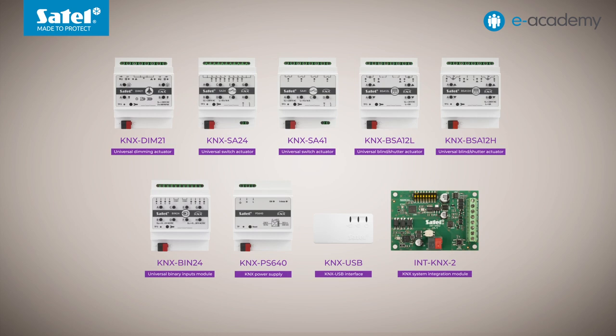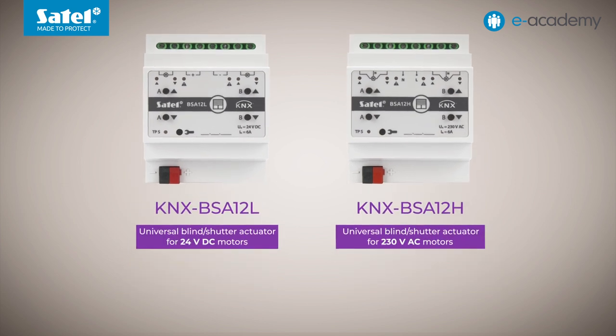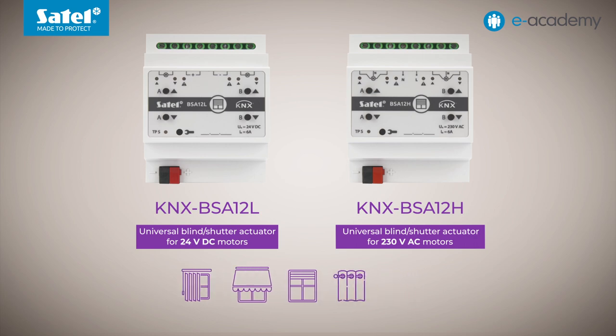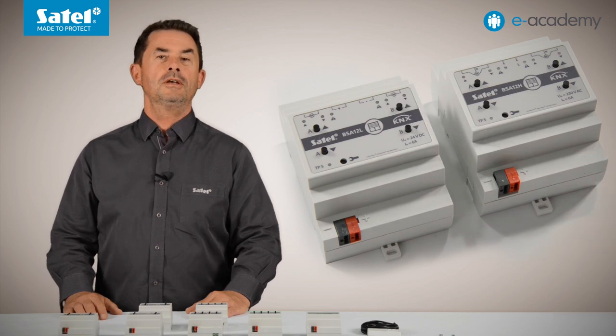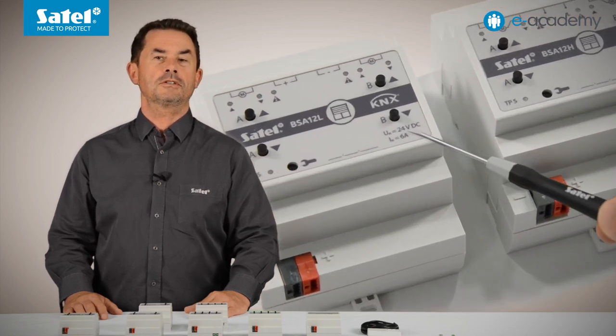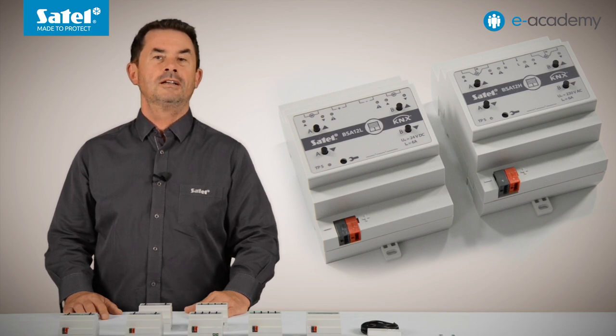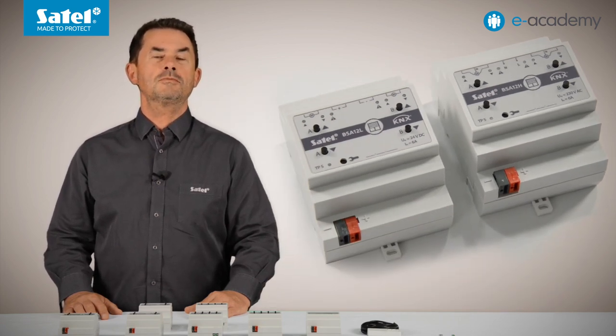Next is a pair of twin modules: the KNX BSA-12L and KNX BSA-12H blind actuators. With these actuators, we can precisely control the position of various types of curtains, such as roller blinds, awnings, or horizontal and vertical blinds. They will also prove successful in controlling electrically powered curtain rails, windows or simple motorized valves. Each of these modules has two independent channels. The KNX BSA-12L is designed for 24 volt DC drives, while the KNX BSA-12H is used for devices with 230 volt AC motors. These modules enable very precise control of blind slats or the height of curtains, solving the problem of blinds or shutters set at different levels in the same room.